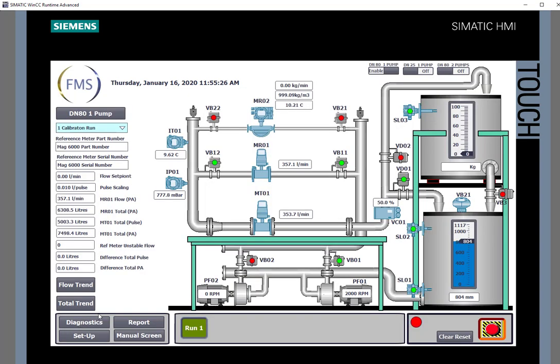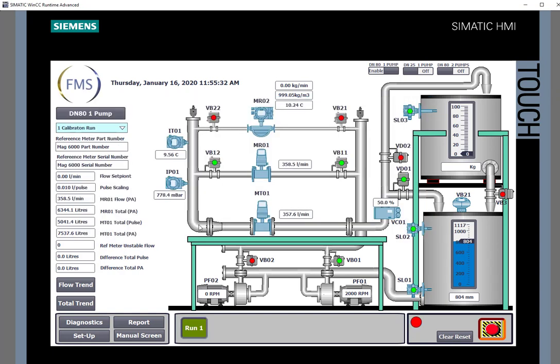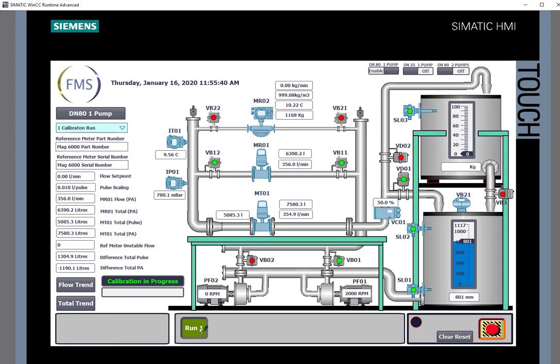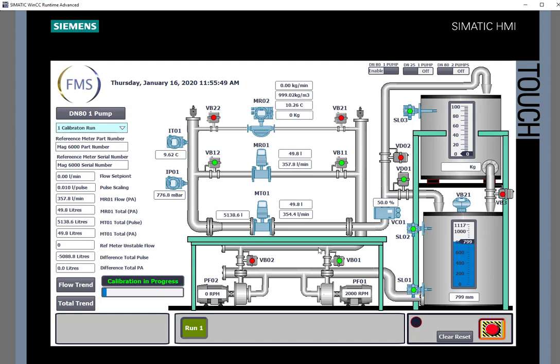I can also look at the total trends to make sure those are on track. When I'm happy that the air has been pushed out of the system we simply click on the calibration button and that will record the two totalizer values or three if you include the high speed counter and it will push those into a report.